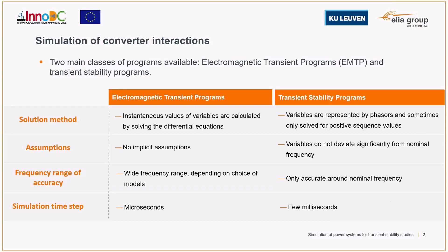Typically, EMTP has been used to study electromagnetic transients, which are located in the high end of the frequency spectrum, while transient stability programs are generally used to study electromechanical transients associated with the behavior of synchronous machines, which tend to be slower in frequency.